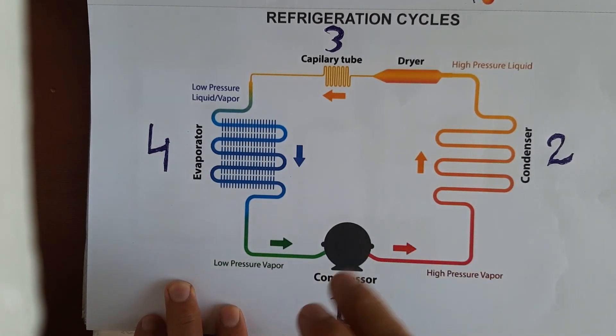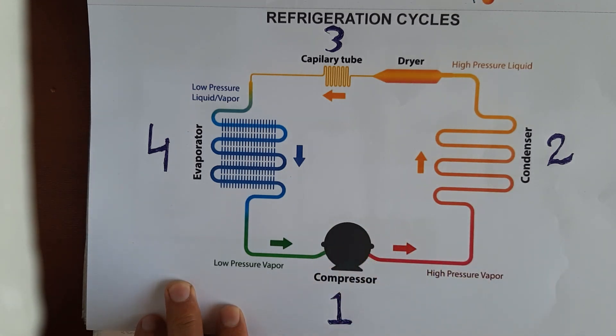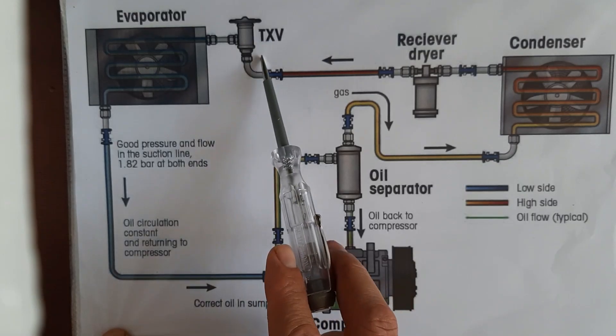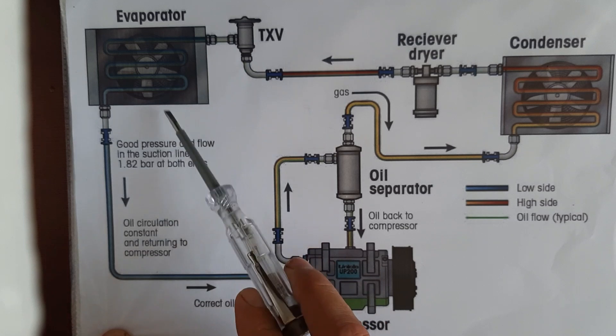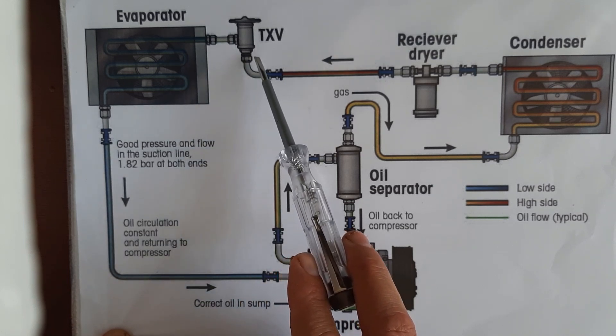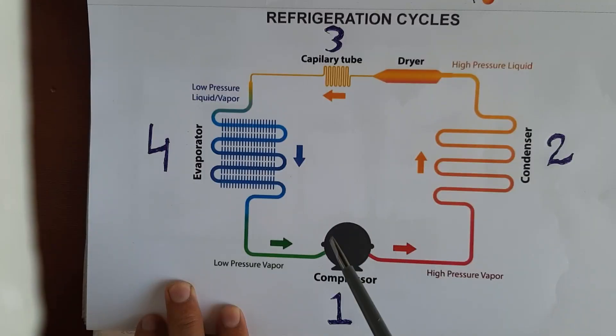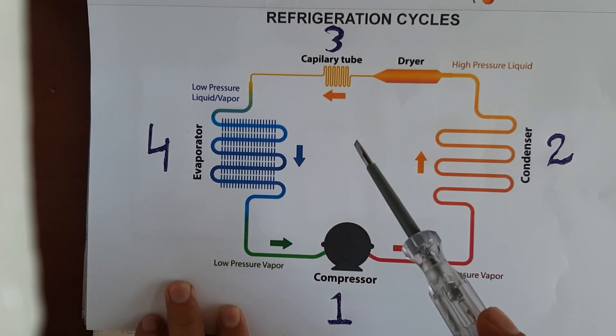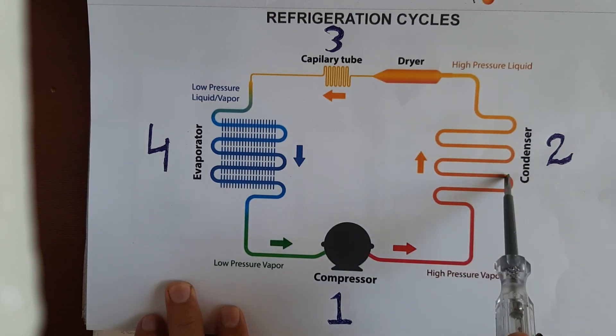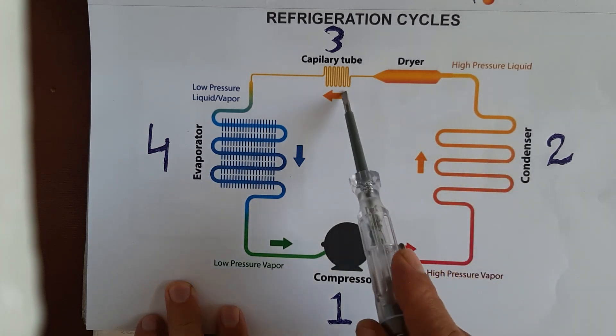Once you go above 3 or 4 tons, the difference is that small units use a capillary tube while bigger units use a TXV — a thermostatic expansion valve. That is the only difference; the rest of the refrigeration cycle is the same for chillers, freezers, cold rooms, and all vapor compression systems.